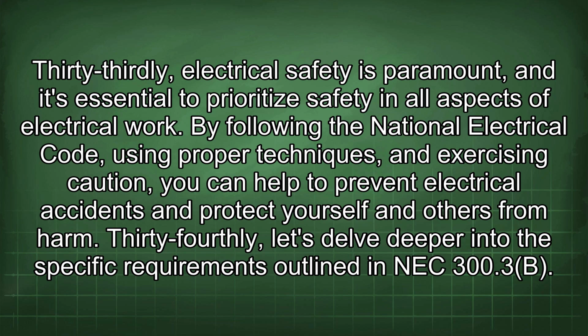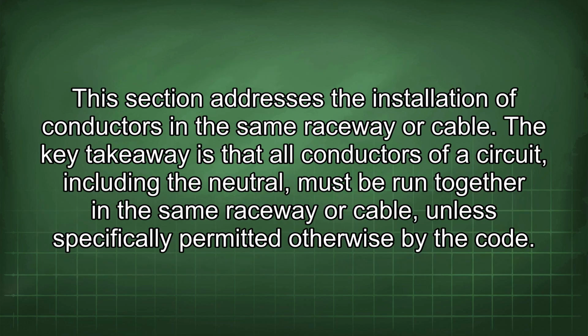34thly, let's delve deeper into the specific requirements outlined in NEC 300.3(B). This section addresses the installation of conductors in the same raceway or cable. The key takeaway is that all conductors of a circuit, including the neutral, must be run together in the same raceway or cable unless specifically permitted otherwise by the code.